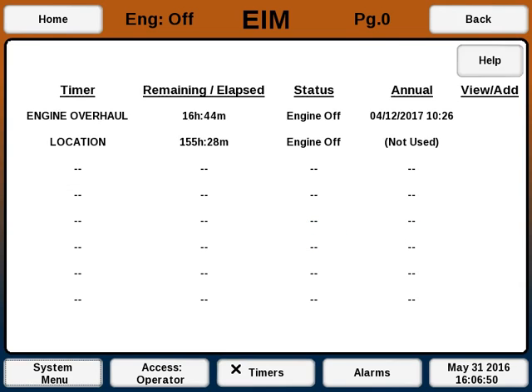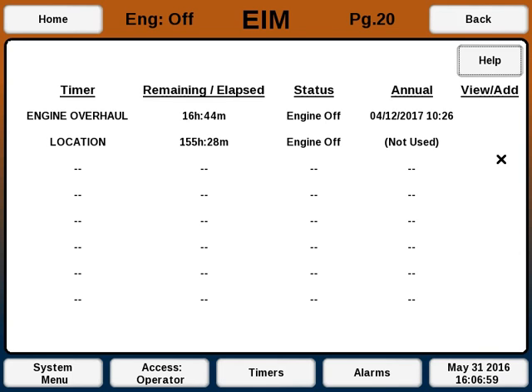The Timers button shows Global Timers. Timers can be added if you're in Setup or higher for any need you choose, and they can count up or down on real hours or runtime hours. These are both count-up timers on runtime. For instance, I could be counting up how many hours have elapsed since the engine was overhauled — when it's overhauled again, in the Timers screen I can reset it.